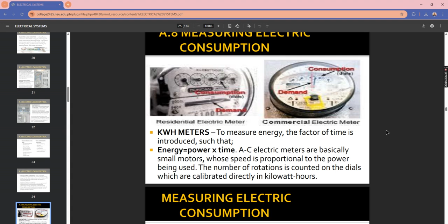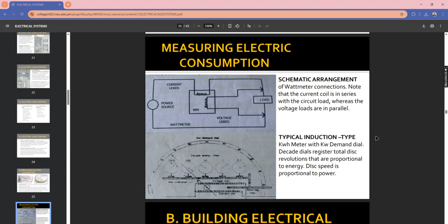Okay, so this is the schematic arrangement on how a watt meter connects. This is the current coil in series with the circuit loads, where the voltage loads are in parallel. And the typical construction, where the kilowatt demand dial and decade dials register the total disk revolutions proportional to energy, with the disk speed proportional to power. If the power is large, the wattage meter spins faster - when consumption is high.